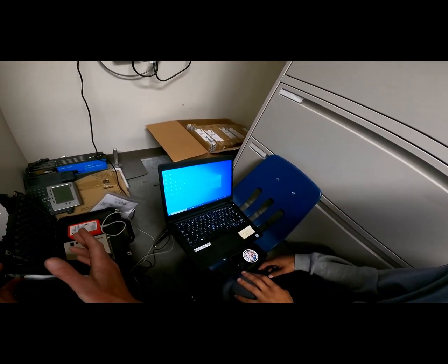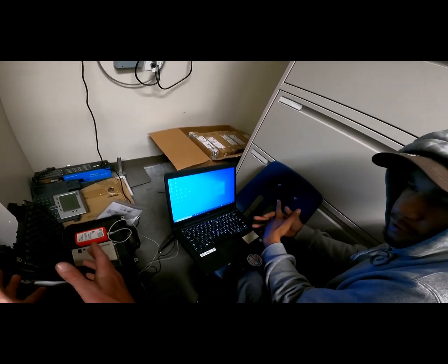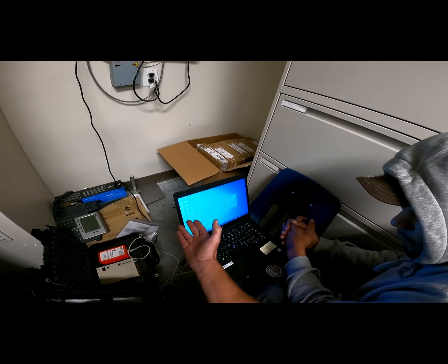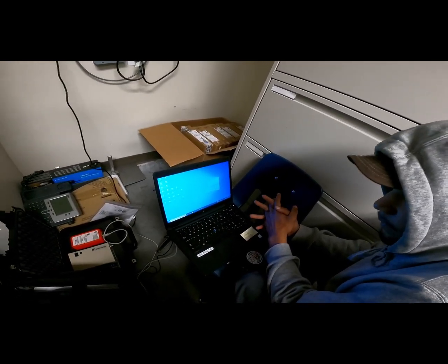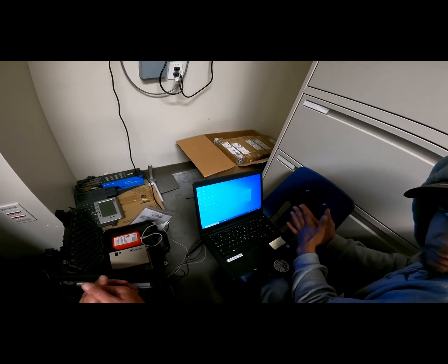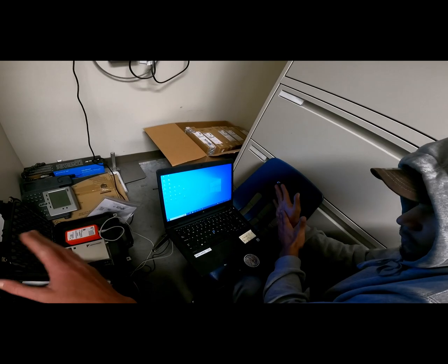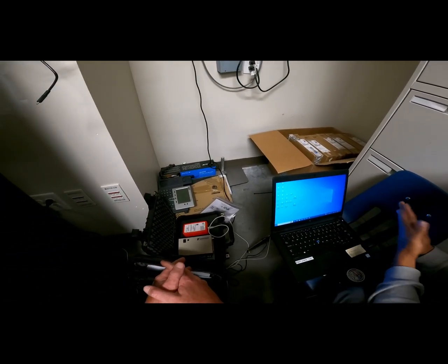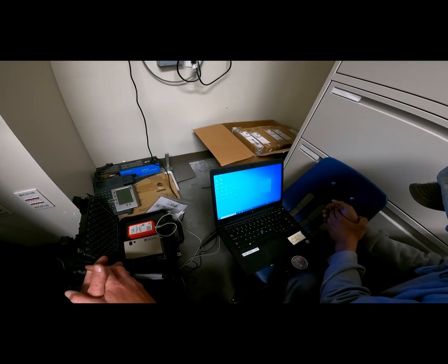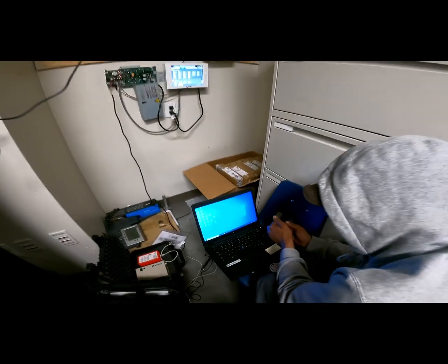Now, if you were to see something that you thought was crazy, we'll call you. You would save it, and then I would be able to get that file from you, and I would import it into my maintenance tool, and pull it up and look through all the data. I can look at the refrigeration diagram. I can look at the data minute by minute, and it won't be too long before we get you guys trained up on how to interpret all those different values. But that's pretty much it.